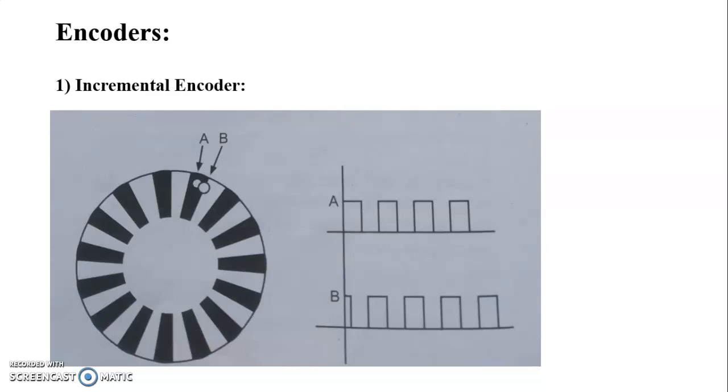Each time the encoder is powered on, it begins counting from 0 regardless of where the shaft is. Initial homing to a reference point is therefore inevitable in all positioning tasks, both upon startup of the control system and whenever power to the encoder has been interrupted.